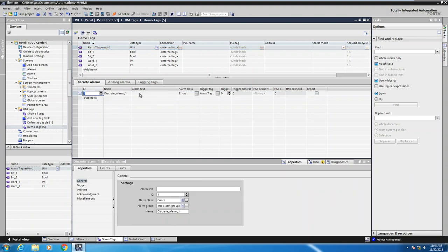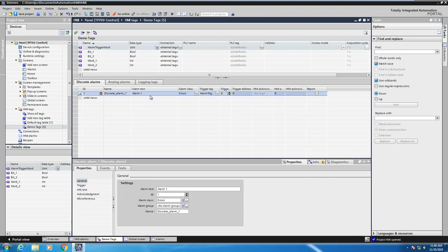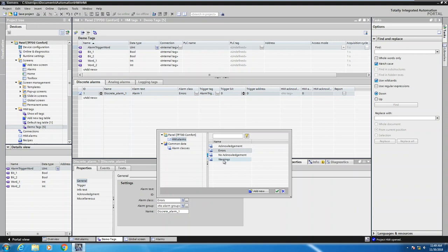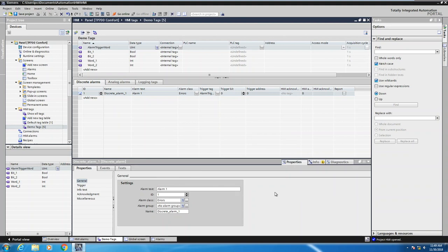I'll double-click on Add New, then add in the alarm text. I'm going to keep it simple and call my first alarm Alarm 1. When you have the alarm selected, you can fill in information in the table editor and see the different columns available, or you can use the inspector window to configure the alarm. In the inspector window under alarm class, it is defaulting to Errors. Errors require acknowledgement. If I press the browse button, there are two alarm classes: Errors and Warnings. Warnings do not require acknowledgement. I'm going to keep Errors selected, so this alarm will require acknowledgement.